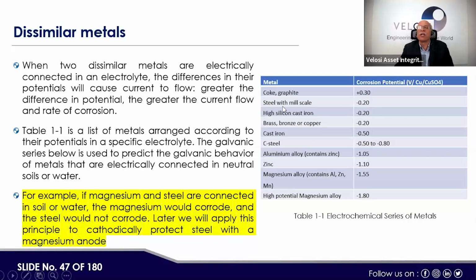Here is the potential scale - coke graphite is plus 0.30, magnesium alloy Al zinc minimum is minus 1.55 on the copper sulfate potential scale, and high potential magnesium alloys can be even minus 1.80. Normal steel with mill scale is only 0.20. So these numbers tell us which metallic part is noble and which is non-noble.